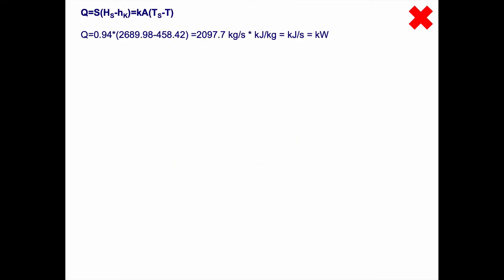I also need the area. To calculate the area, we need to calculate how much energy is transferred. S is 0.94, and we multiply that with the difference between the enthalpy of the steam and the condensate. We get 2097.7 kilowatts. I check the units to see that it's correct.